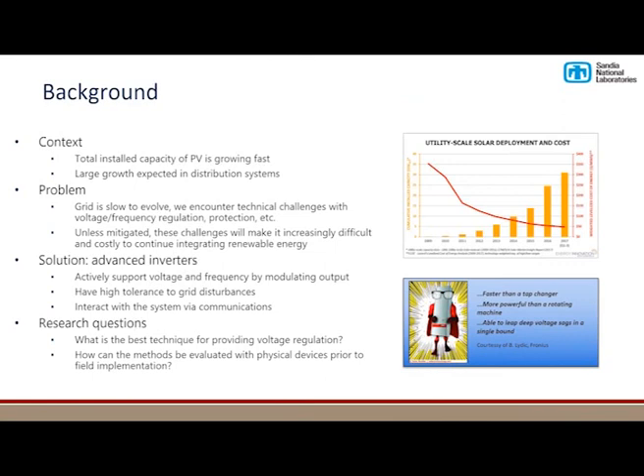The problem is that as we install all these devices, we run into different technical challenges at the distribution level and the transmission level around voltage and frequency regulation and protection, which we just heard a lot about. And we need to come up with solutions to those challenges in order to continue installing renewable energy systems on our grid. One of the obvious solutions here is advanced inverters, which include a suite of grid support capabilities that actively support the grid voltage and frequency by changing their output characteristics.